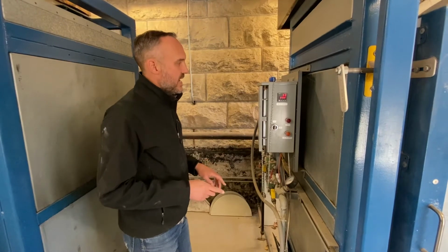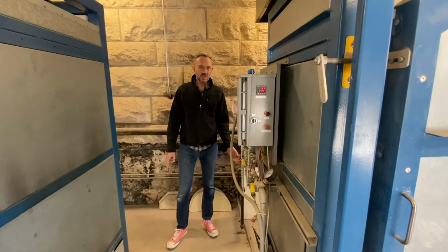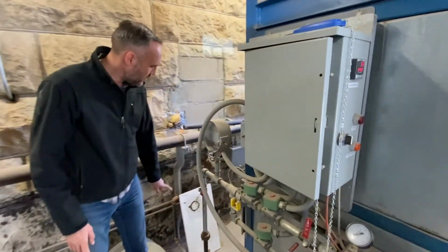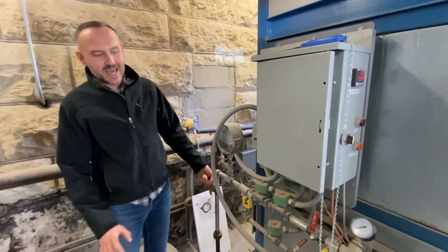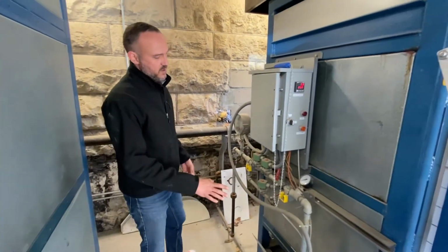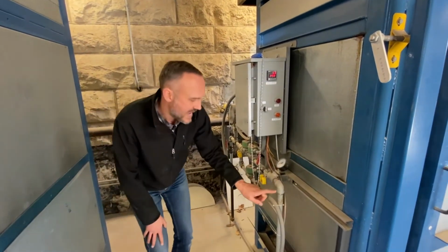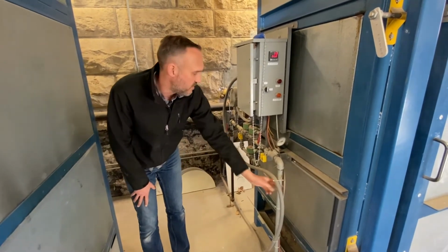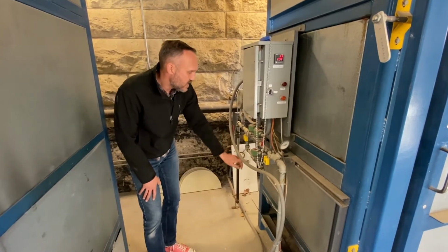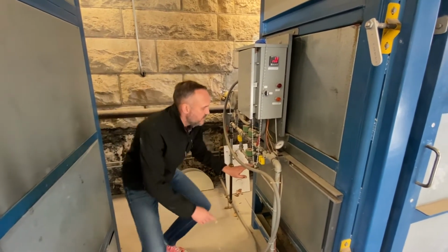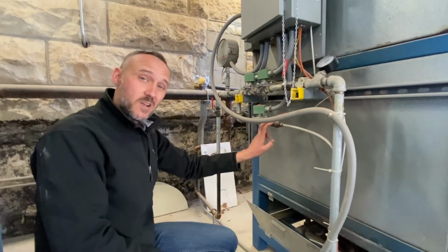So the first step to lighting this, we've got our main box on. We then want to turn on the gas valve over here. Following upstream, we know the main one's on. This would be the next one to turn on. Again, no problems because we've got our thermocouple. As we follow this along, this pipe's much larger. We can notice that. This is our main burner valve right here. But we can also see that the gas makes a T here and comes down to a smaller valve here, right? And this is a smaller line, so we can deduce that this is going to give us less volume. So that's our pilot ring.